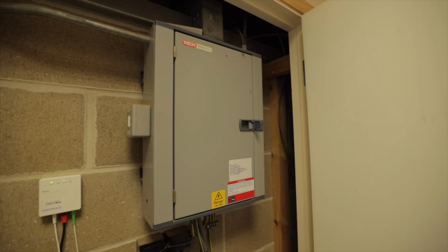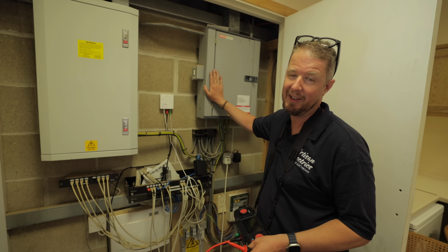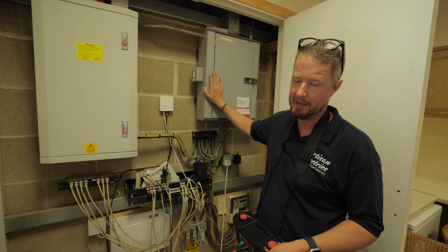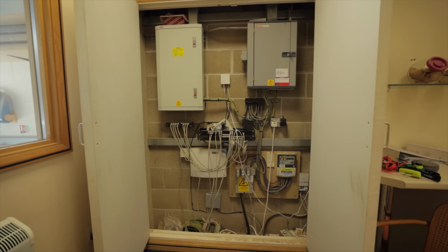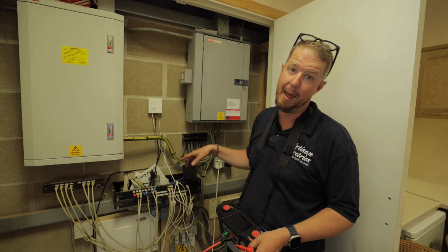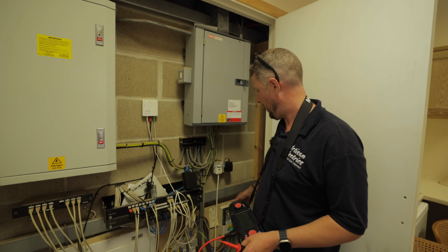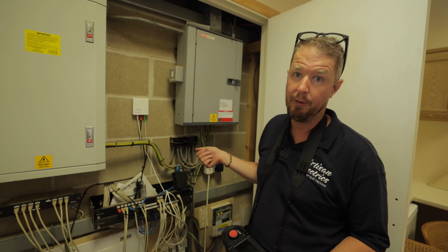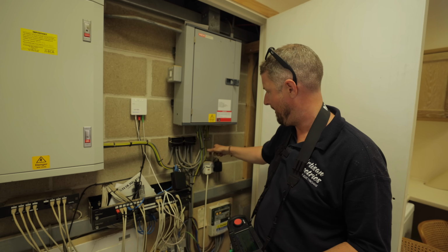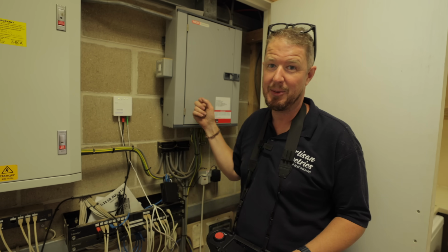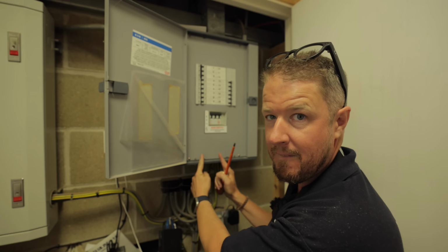So our first test is our ZE, which stands for External Earth Fault Loop Impedance. What we're testing here is the earth fault loop path from here back to the transformer. To do that we have to turn the power off, and we have to disconnect the main earthing conductor, which means we're going to need to take the cover off this.